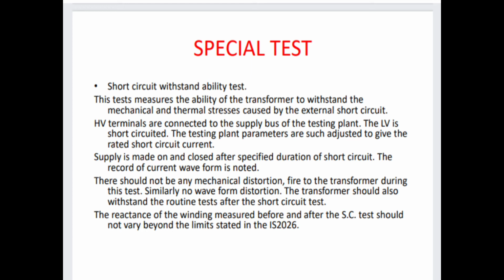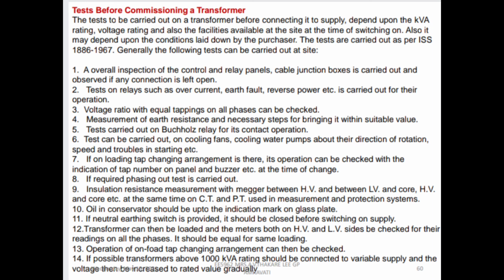The record of current waveform is noted. There should not be any mechanical distortion to the transformer during this test. Similarly, no waveform distortion. The transformer should also withstand the routine test after the short circuit test. The reactance of the winding measured before and after the short circuit test should not vary beyond the limit stated in the IS 2026. So, test before commissioning a transformer.